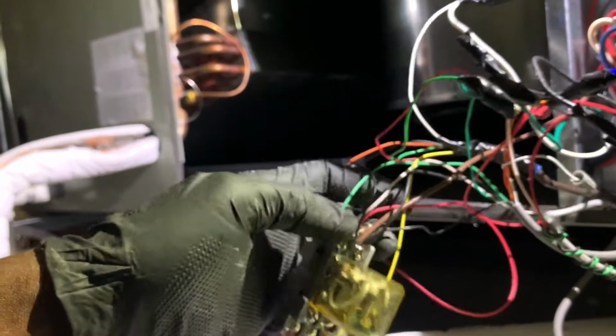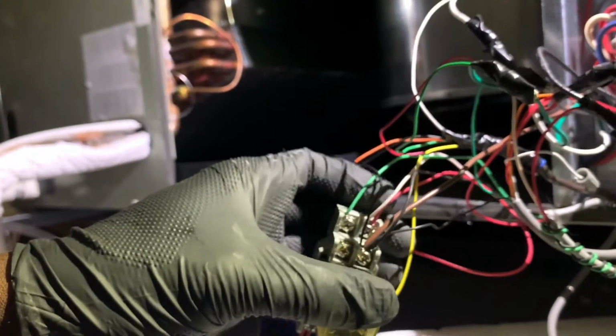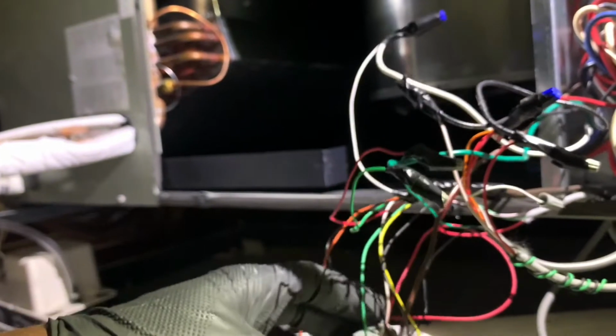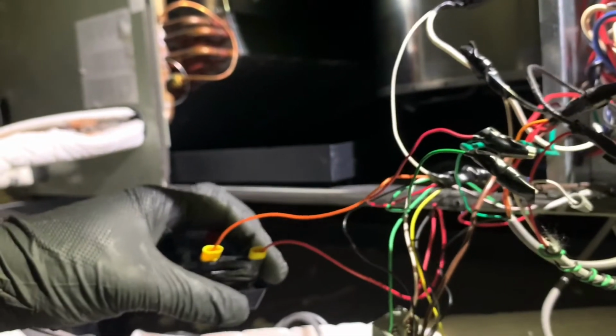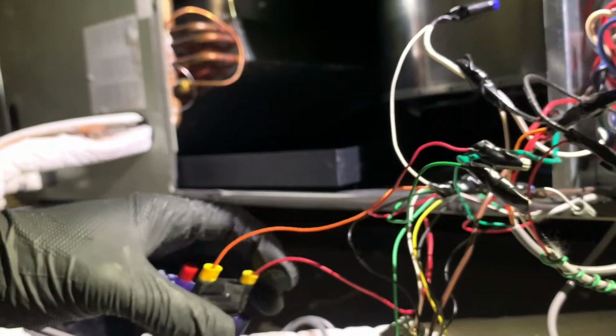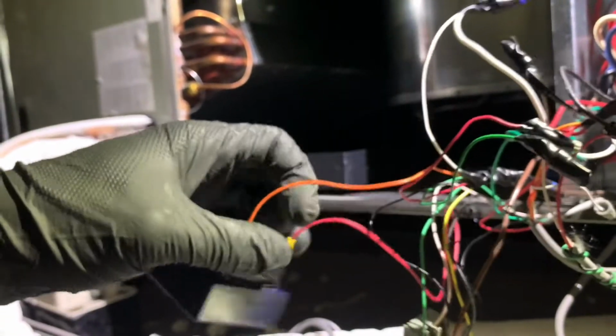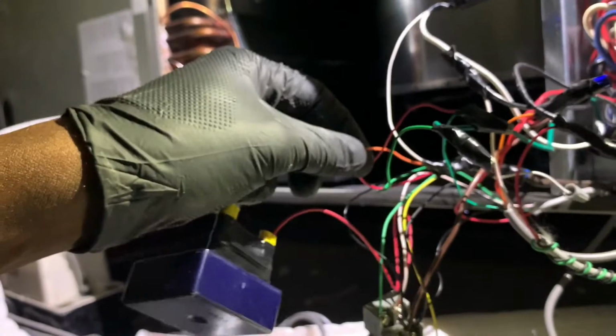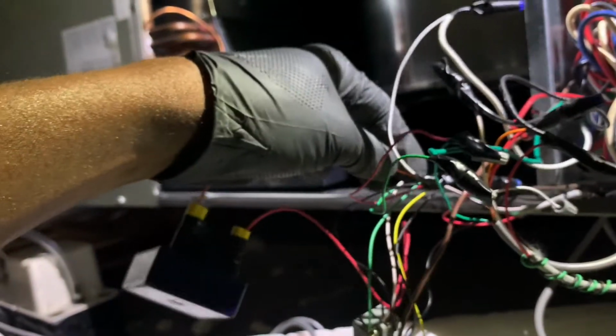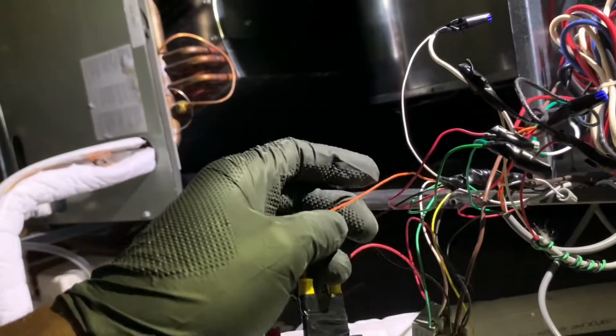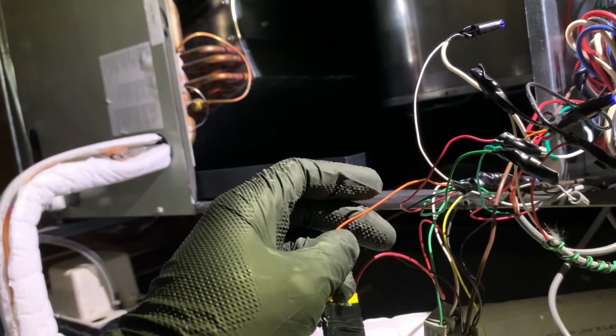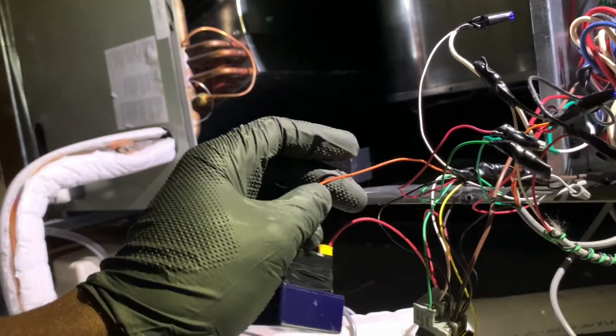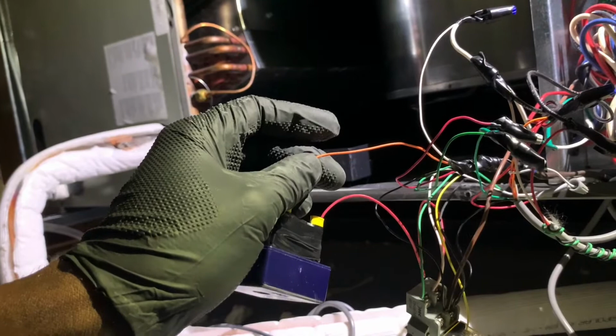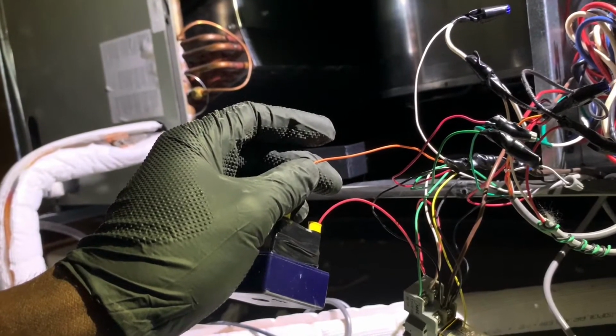Simultaneously, this red wire that's attached to the white wire, same as the cooling terminal that goes outside, comes to this time delay, and then on the other side of this time delay, this orange wire goes back into my thermostat, and that's going to go to W2. Okay, so even though this is, we're going to say this is a two-stage heating, one-stage cooling. So if you get what I'm doing so far, W, or W1, is going to be the primary for the heating, which is the hot water coil or the boiler.